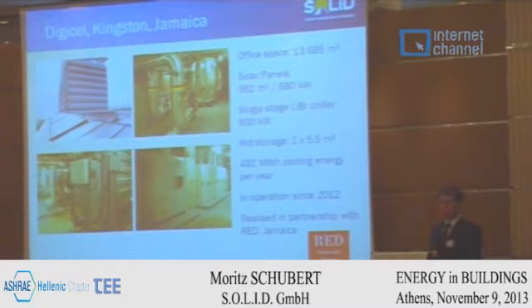It's very important that the cold distribution system, the conventional compression cooling machine, and the solar cooling machine are all commissioned well, because if you don't match the temperatures the compressor needs, the absorption chiller needs, and what the building and inhabitants need, you often run into discomfort levels and too high electricity needs. So it's really important, when starting such a system, to take the time to look at the parameters and adjust them as needed.